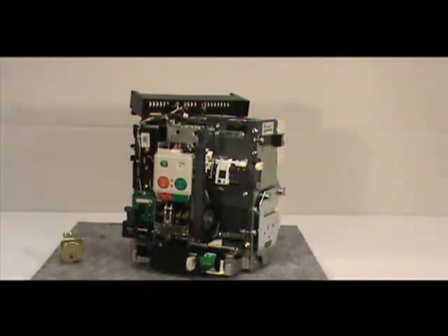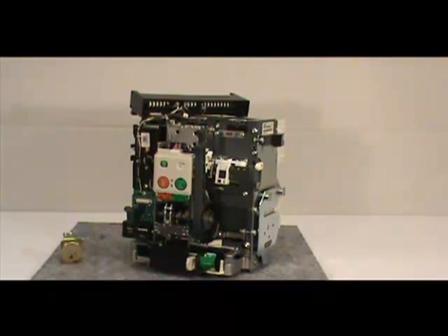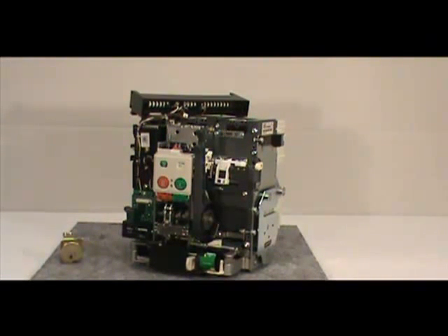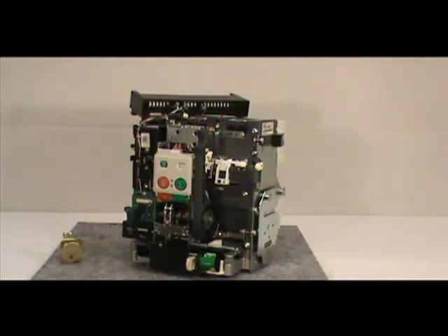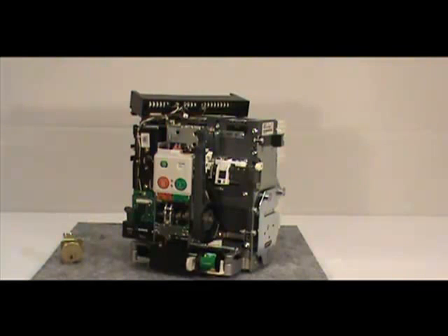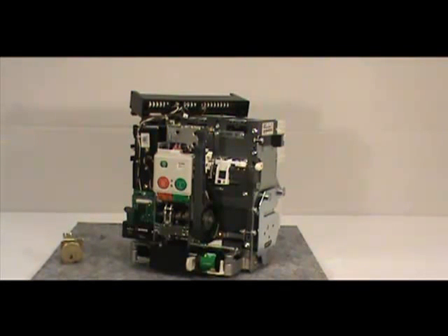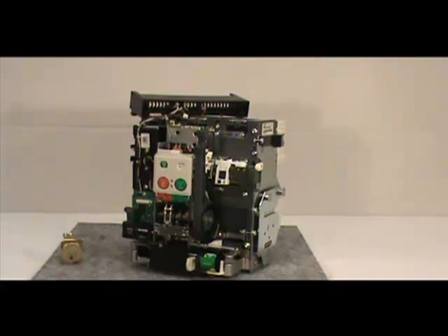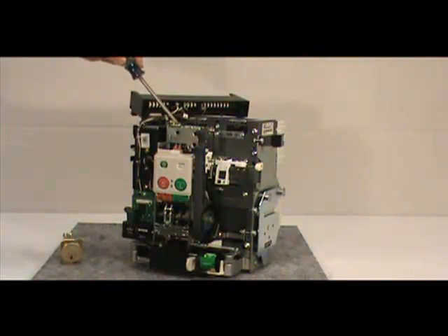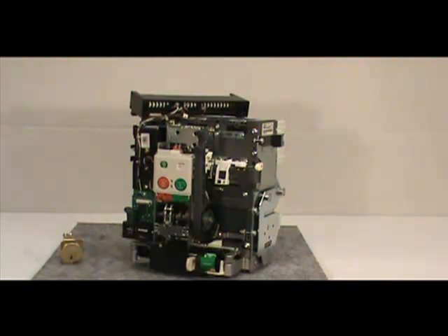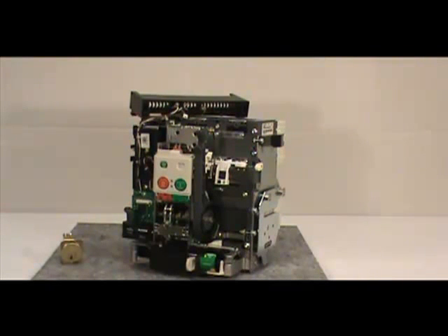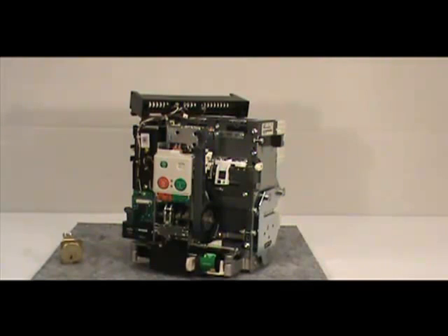We've removed the front cover, shifted the secondary mounting bracket, and assembled the key lock. The last phase of this process involves mounting the key lock assembly to the circuit breaker and ensuring that it's functional. Locate the mounting location, it is right below the secondary mounting bracket. There are two threaded mounting holes in the mounting tab. Using the two mounting screws and two fiber retaining washers, screw the key lock assembly halfway into the mounting location and then stop.